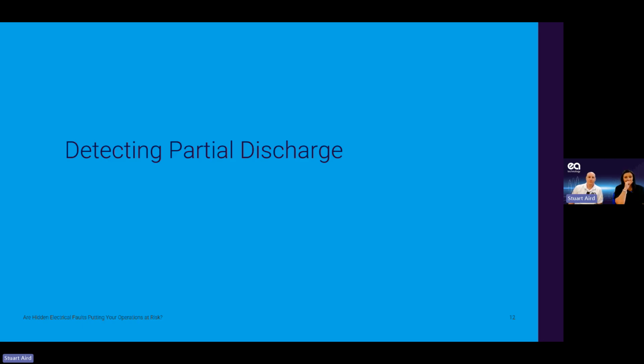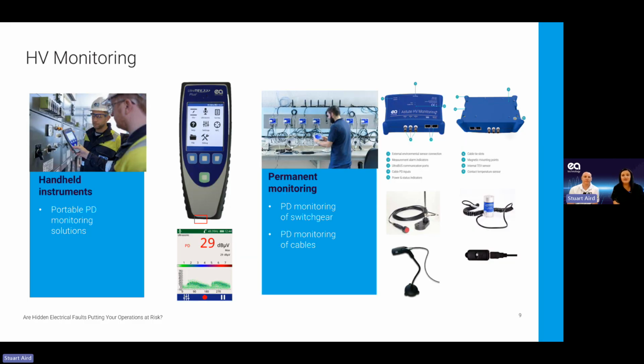So here at EA Technology, we've got two main monitoring solutions for detecting partial discharge. We have our handheld instruments, which are for periodic condition assessments, ideal for routine inspections, with a lower initial investment. And the portable equipment can be used across multiple sites, so it's a lot more versatile when people are on sites doing these monthly or 6-monthly checks, whichever they prefer on their maintenance schedule. We then have our permanent monitoring. The permanent monitoring is continuous 24/7 monitoring, ideal for critical assets because it gives immediate detection of developing faults, and it provides trend data for early warnings of faults that are coming.